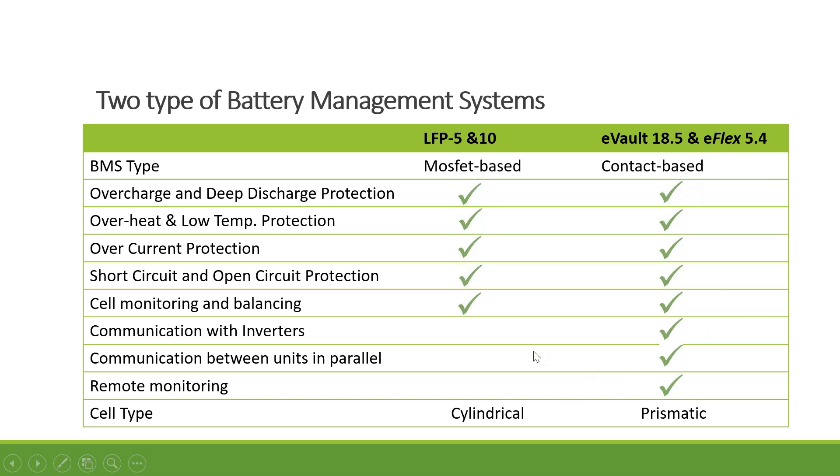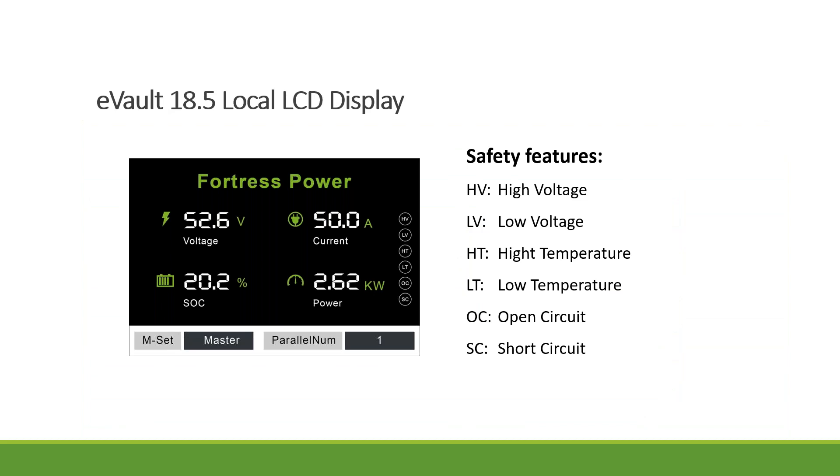There are three types of cells available on the market: cylindrical, pouch, and prismatic. For the 5 and 10 we use cylindrical — smaller and more flexible. The prismatic is a rectangular shape, more robust especially for large applications. Here's how the monitoring looks on the eVault. You can see the voltage, state of charge, current, and power. There are also error codes — if for whatever reason you overcharge the battery, the high voltage warning will come up. This makes it different from lead acid or other lithium batteries where you might not know what's going on.